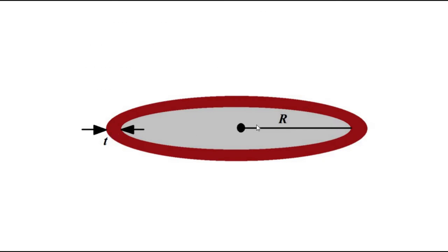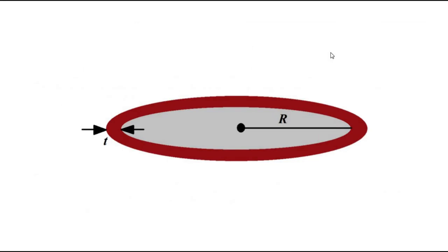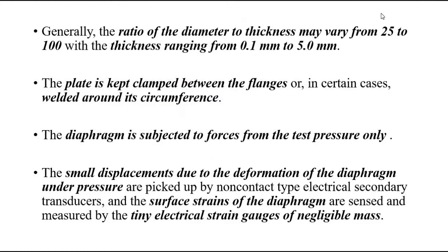The ratio of diameter to thickness is very important for diaphragm-type pressure measurement devices. This ratio generally varies from 25 to 100, and the thickness ranges from 0.1 millimeter to 5 millimeters.